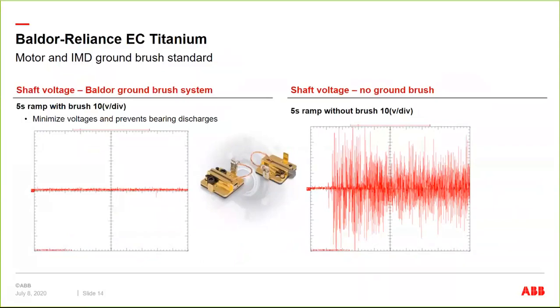This is just kind of a visual. I don't need to spend a lot of time on it, but this is why you want a shaft grounding system in a motor. This kind of noise you see here on the right is what we call common mode voltage. That causes electrical discharges and bearing damage, and you put in a shaft grounding brush here on the left, and that basically eliminates the noise and the concerns you might have with common mode voltages.